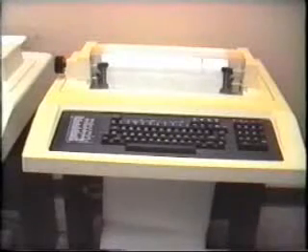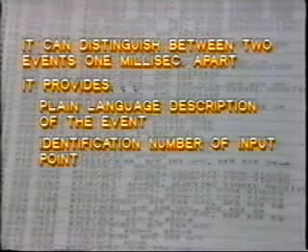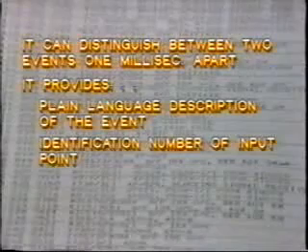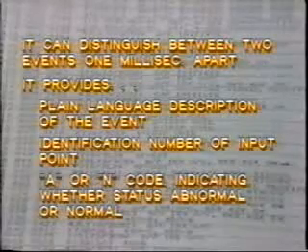The SER is constantly monitoring the status of each input point and prints out a detailed record whenever the status changes. A typical SER printout gives the exact time of the event down to the millisecond. It can distinguish between two events occurring one millisecond apart, and provides a plain language description of the event and the identification number of the input point.